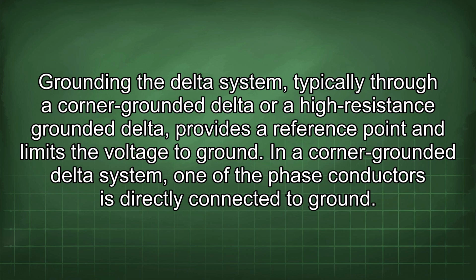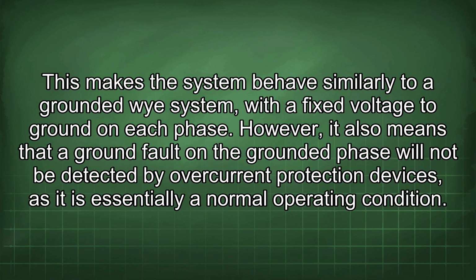In a corner-grounded delta system, one of the phase conductors is directly connected to ground. This makes the system behave similarly to a grounded Y system, with a fixed voltage to ground on each phase. However, that also means that a ground fault on the grounded phase will not be detected by overcurrent protection devices, as it is essentially a normal operating condition.